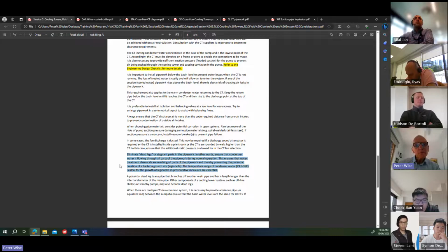This ensures that the water treatment chemicals are reaching all parts of the pipework, thereby preventing the potential creation of bacteria growth. So you can get this Legionella growing in dead legs if there's no water flowing through there. The temperature range of condenser water, as I said, 29.5 to 35 degrees, is ideal for the growth of Legionella. So we need to take all measures to prevent it.